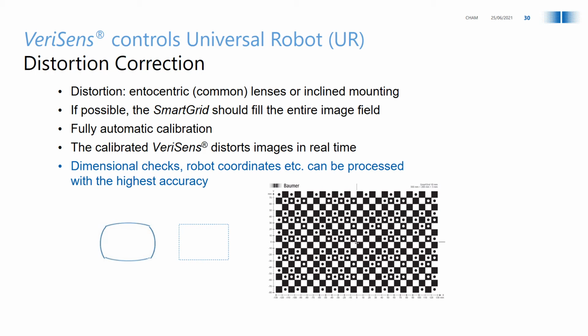So it's very common with lenses or inclined mounting positions, and all you have to do is make sure that you put the smart grid under the camera, and if you just press calibrate, the VeriSens understands the distorted image and makes the correction for it internally, enabling you to give the highest accuracy of dimensional checks and give you the robot coordinates very easily, because it knows this calibrated chessboard design.